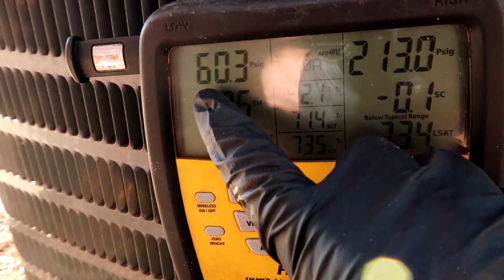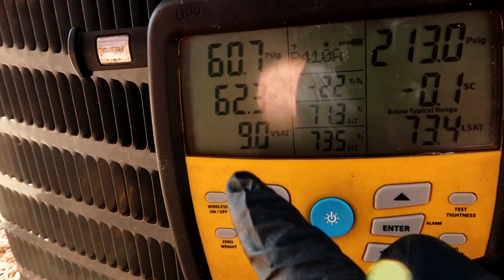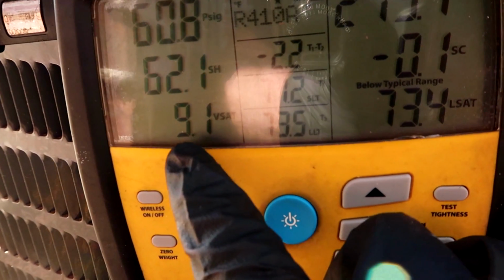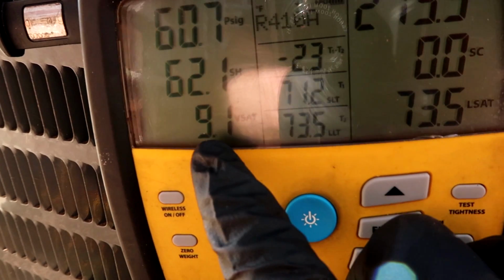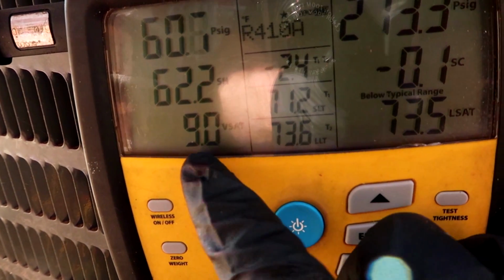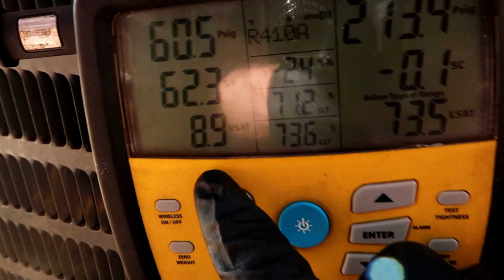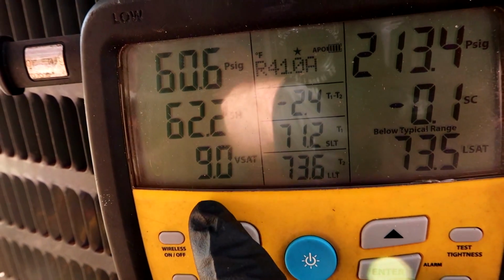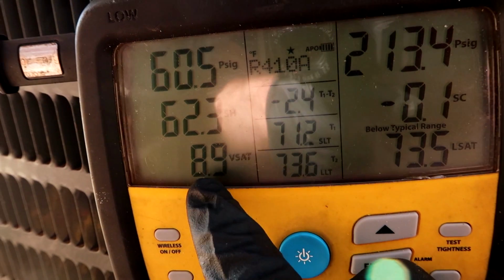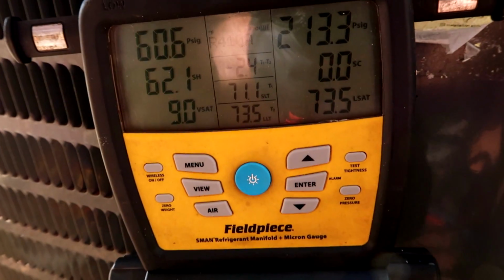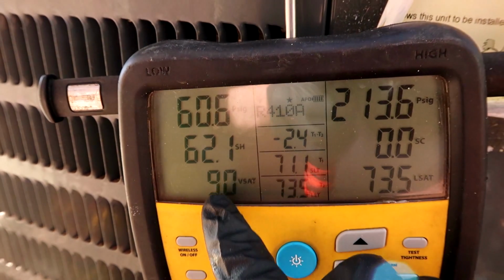59 psi, 60, that's really low. And for you new guys, I also keep an eye on this number here. See, that's the saturation, 9 degrees. That's why it freezes and turns into ice, because it's below 32. Below 32 is freezing, you know, and that's at 8 degrees. So that's why all that ice comes up. I keep an eye on that number as well.